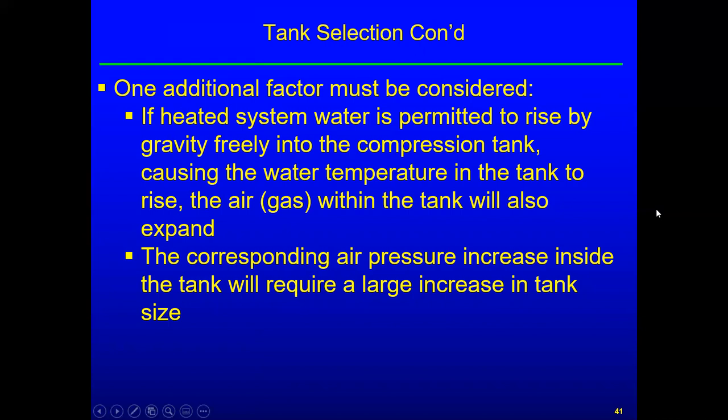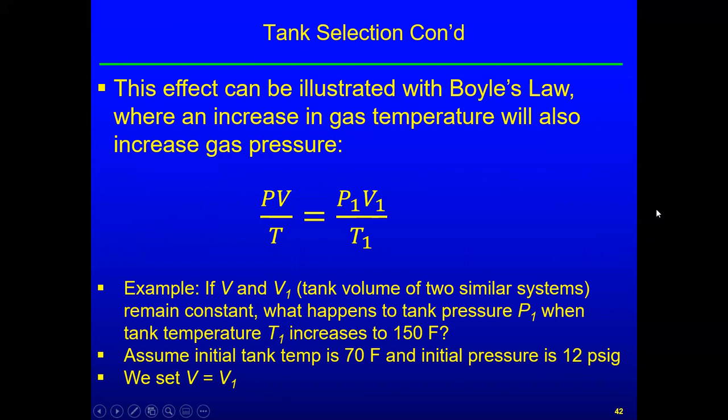because if this is high temperature water, we could have 200, 250 degree water circulating through there, and we don't want that hot water to get up in that compression tank, because then it'll cause that air to expand, and then we'll have to have a much bigger tank if we let the water get hot. So that's kind of the game here. And he goes through this basically ideal gas situation.